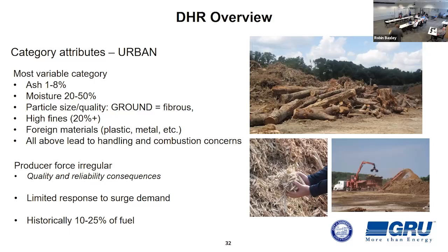With that, it's also prone to have some foreign materials in it. It could have plastic, it could have metals in it. We try to sift all that out. The aggregator tries to pull all that out and sort it, but you don't get 100% of it. Those variations also lead to handling problems and combustion concerns, for the very same reasons, because you don't know what you're getting. You're grinding it and putting it together, but it's such a various quality of material in there. The range is very high. It's also very irregular. Some of that is, again, if it's a storm and you have a lot of down limbs and trees, that available volume could be very high, or in a dry season, depending on the time of year, that volume could be very low. So irregular quantities, and it has a limited response in surge demand, a little more than the mill residues, but still very limited.